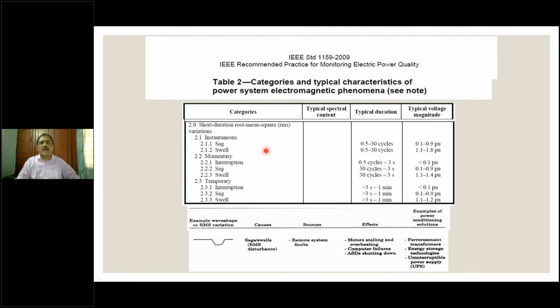As you can see here, IEEE 1159 also talks about voltage sag for 3 different durations: one is called instantaneous, the other momentary, the third temporary. From 0.5 cycle to 1 minute is how they have divided this into three categories. Typically, solutions are available after 2 milliseconds. From the 3rd millisecond till 30 seconds, not 1 minute, it is possible to hold the dip in voltage, or the 110, 120% swell, such that sensitive electronic equipment will not trip.